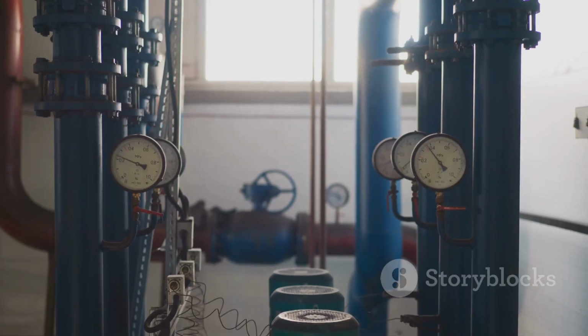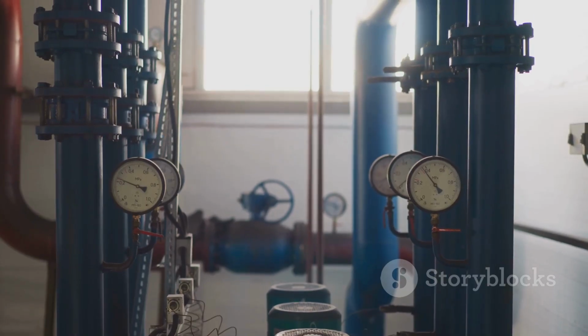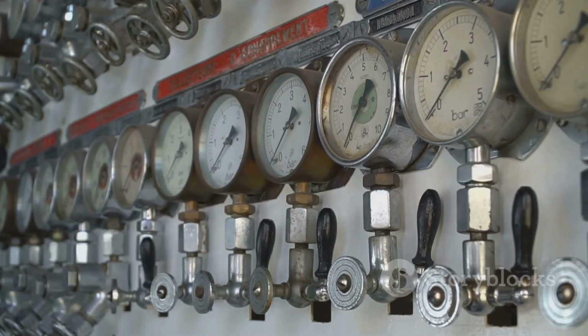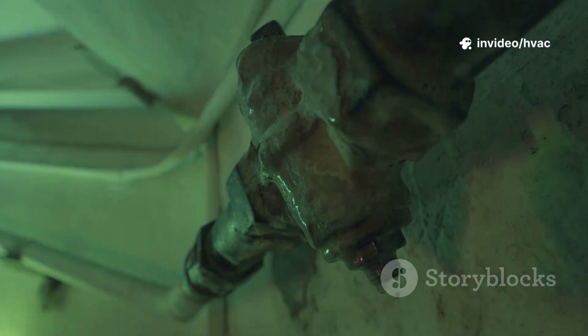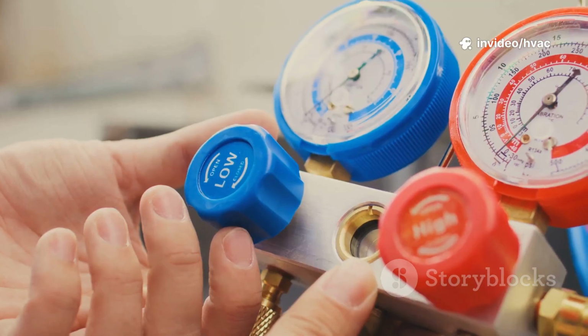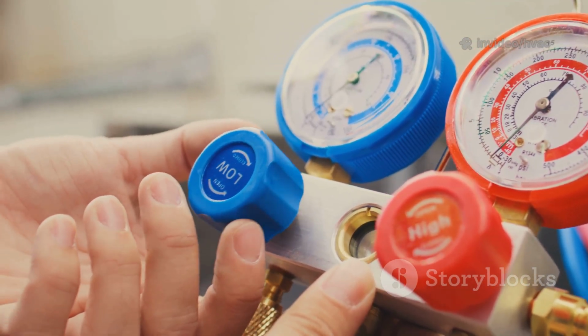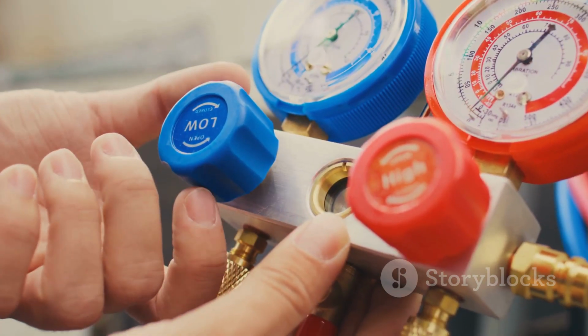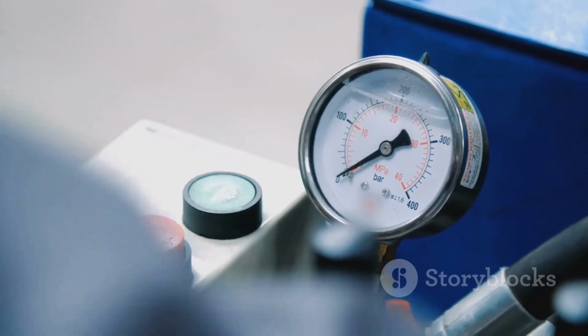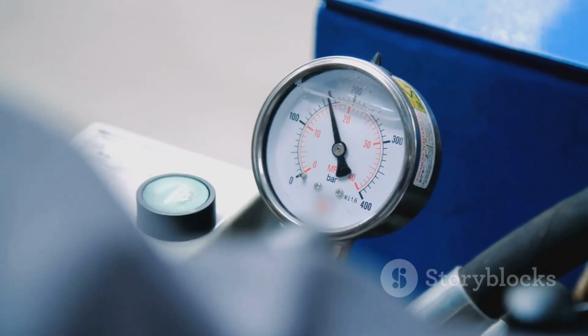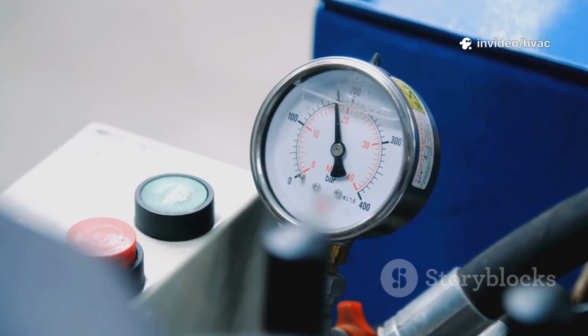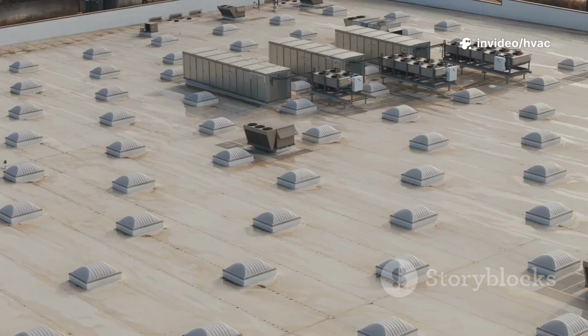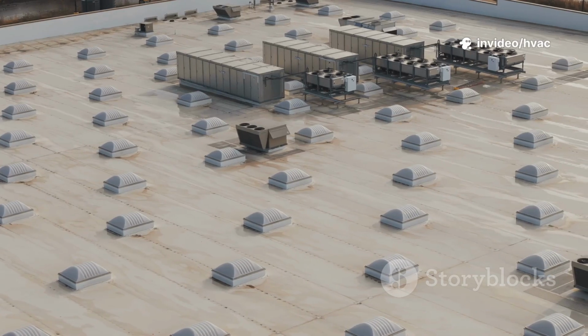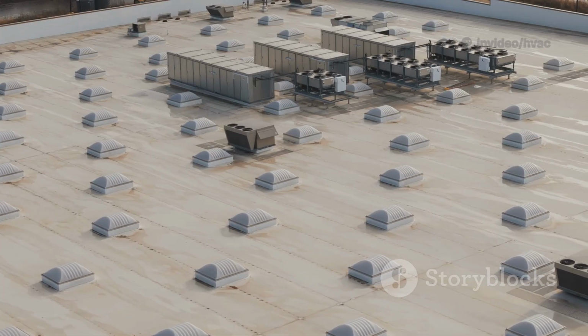In a large building, many valves are opening and closing all the time. This causes the water pressure to go up and down constantly. A traditional control valve would let too much or too little water through when this happens. The PICV, however, has a built-in regulator that automatically adjusts to these pressure changes. This ensures that the flow rate you set is the flow rate you get, providing stable and predictable performance for the HVAC system. You can find PICVs installed in many different types of commercial and institutional buildings.